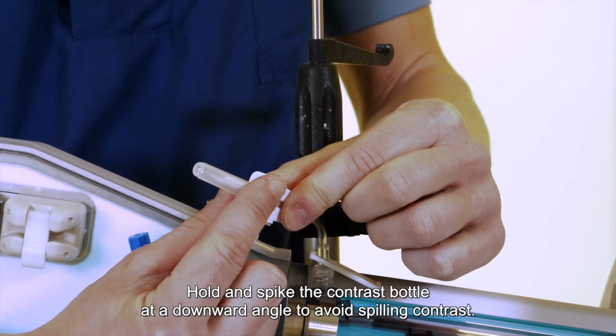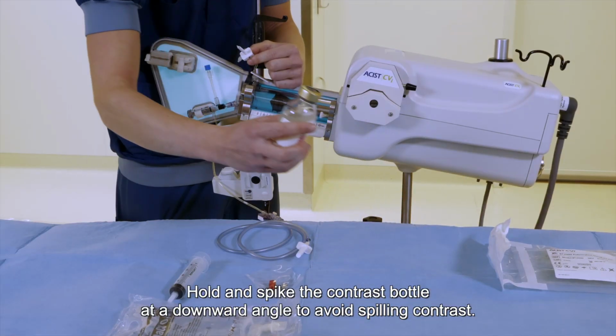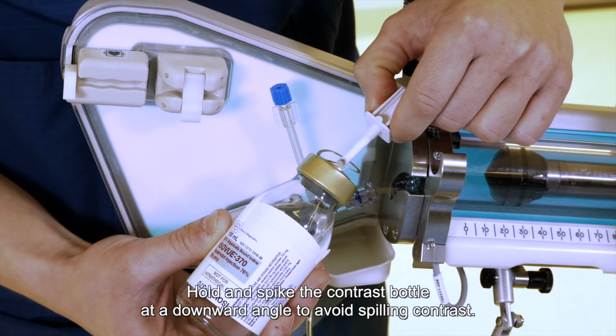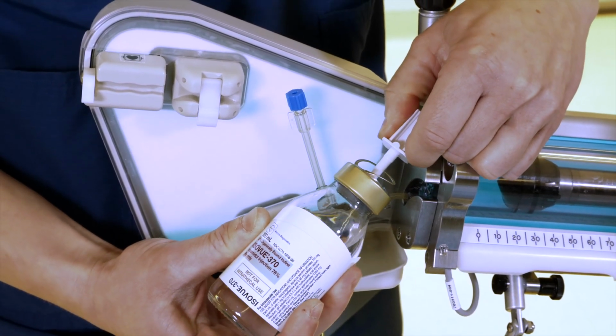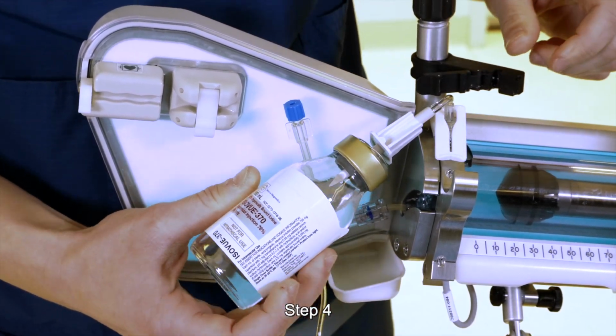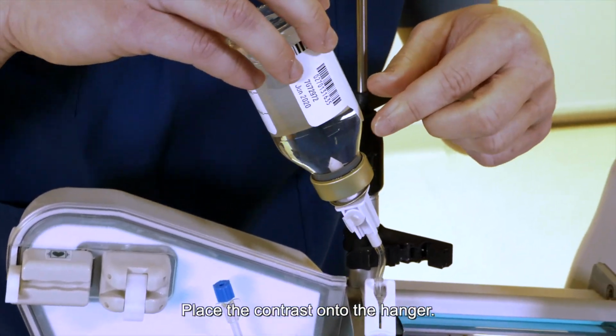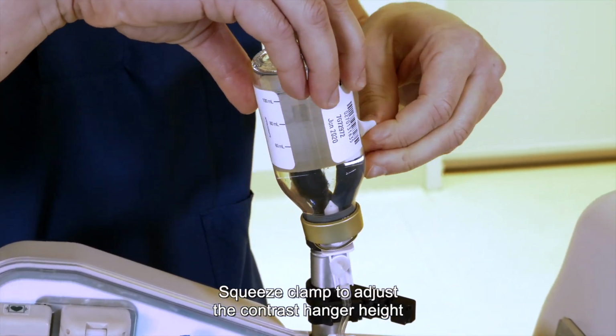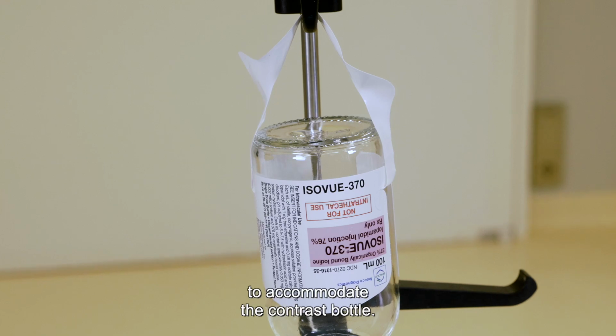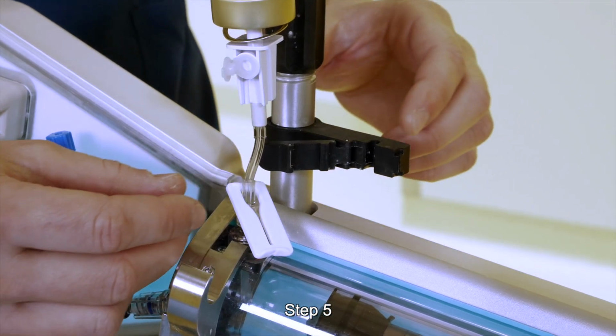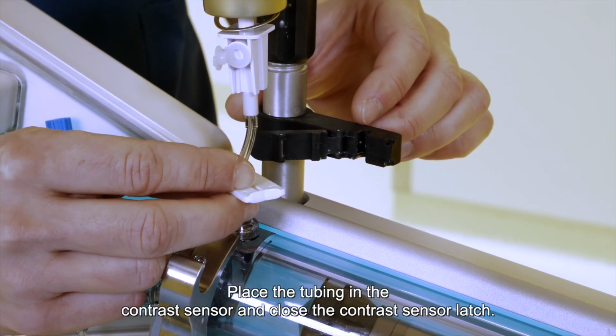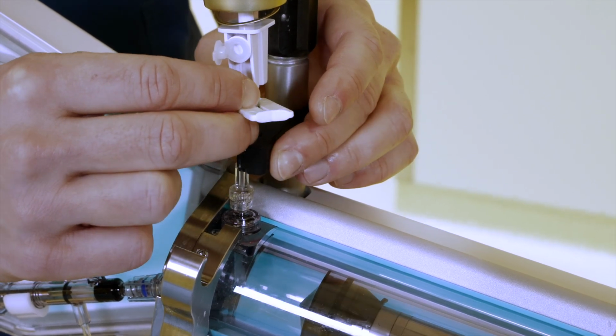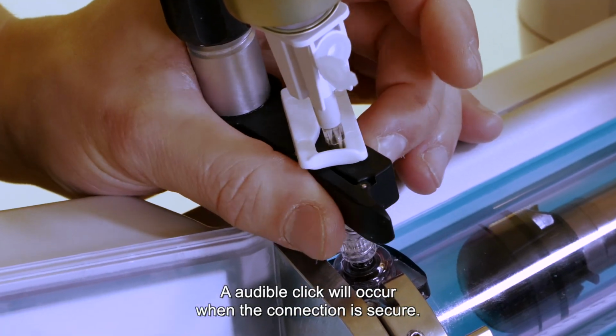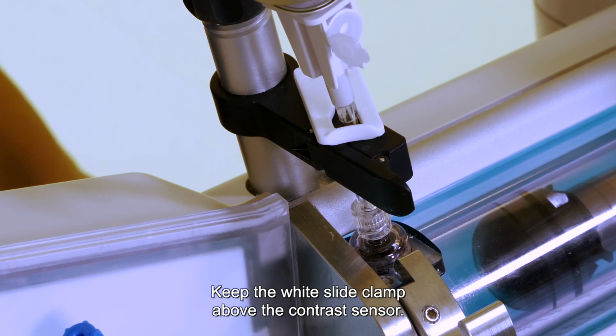Step 3. Hold and spike the contrast bottle at a downward angle to avoid spilling contrast. Step 4. Place the contrast onto the hanger. Squeeze clamp to adjust the contrast hanger height to accommodate the contrast bottle. Step 5. Place the tubing in the contrast sensor and close the contrast sensor latch. An audible click will occur when the connection is secure. Keep the white slide clamp above the contrast sensor.